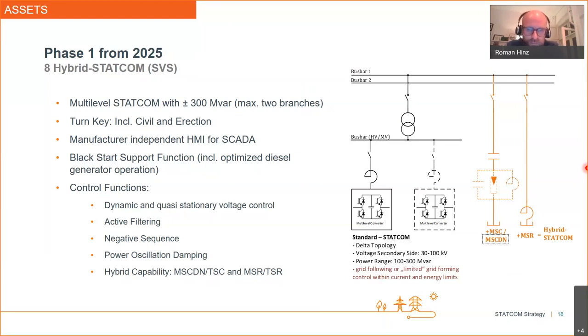And what we also expect when we tender this kind of STATCOM right now is a voltage on the secondary side of something between 30 and 100 kV. So this means when we tender this, and also when you want to specify this, we cannot specify standard components. This was a little bit of an issue for us. But anyhow, I think we can handle this, because we can give the manufacturers some freedom in this area.